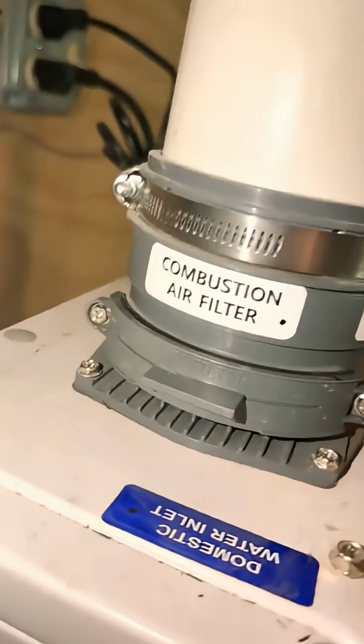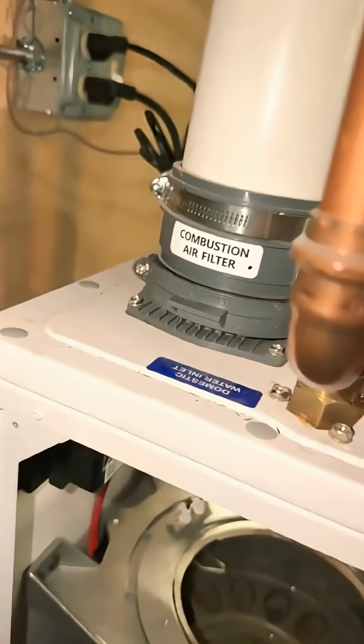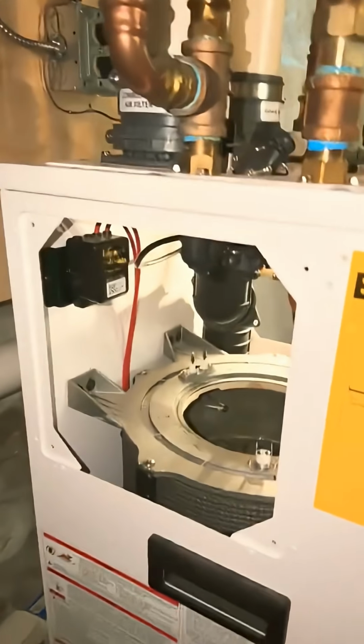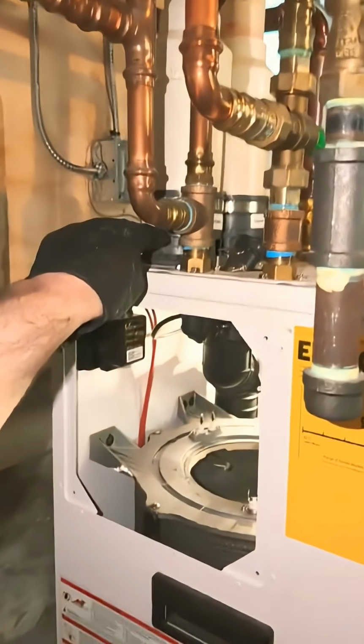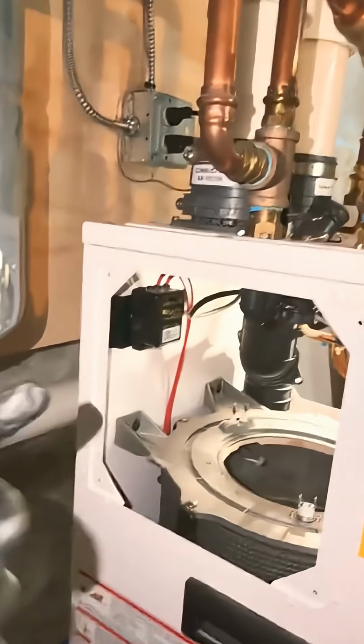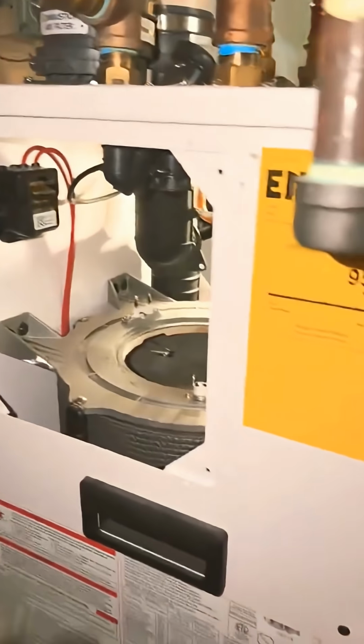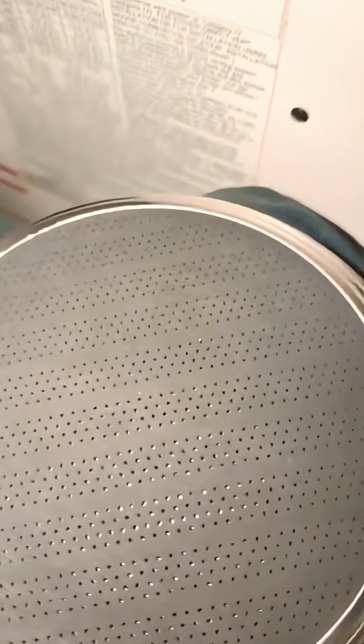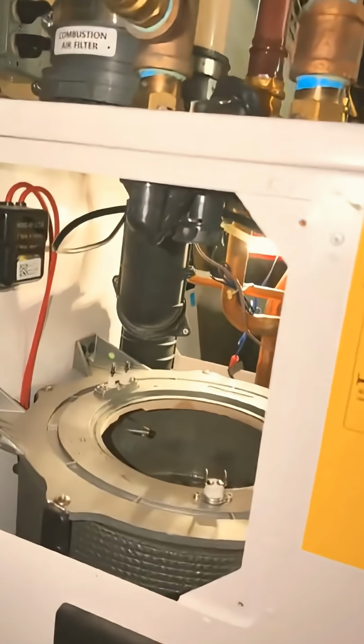good shape. The air intake does have a filter on it, and if it's been a while, a year, 2 years since the last maintenance, that screen gets really plugged up, and it was very dirty when I took it out to clean it, and that can cause these mats to overheat and to burn rich. So that's something, a maintenance on a Bradford White boiler, or mainly this boiler as well, just for that reason of that mat. It's sensitive to too much heat, especially for a long period of time.